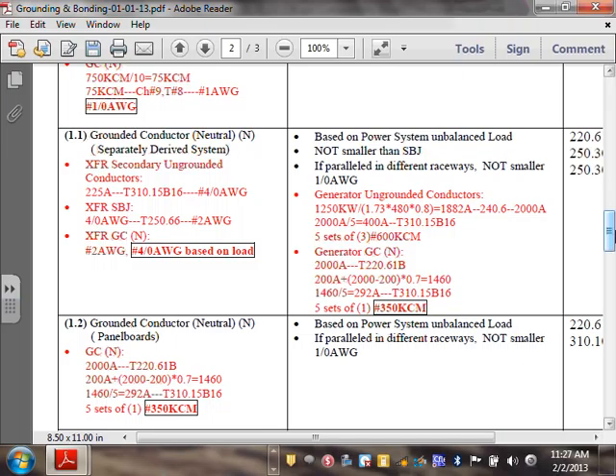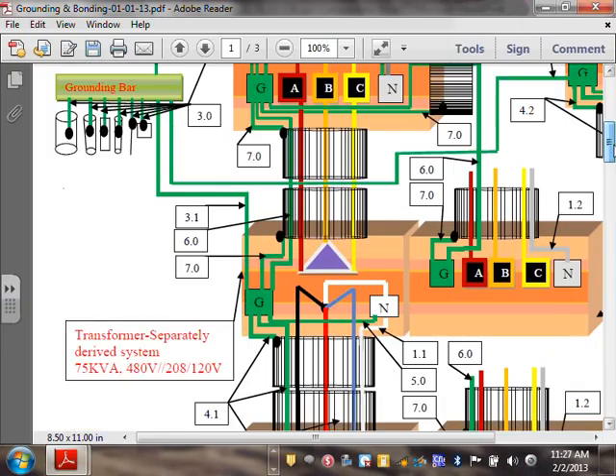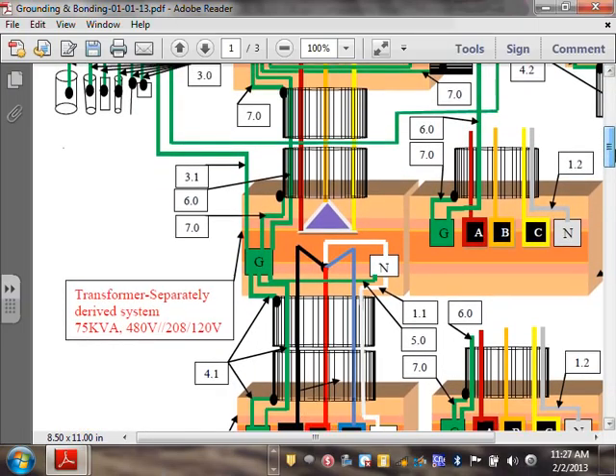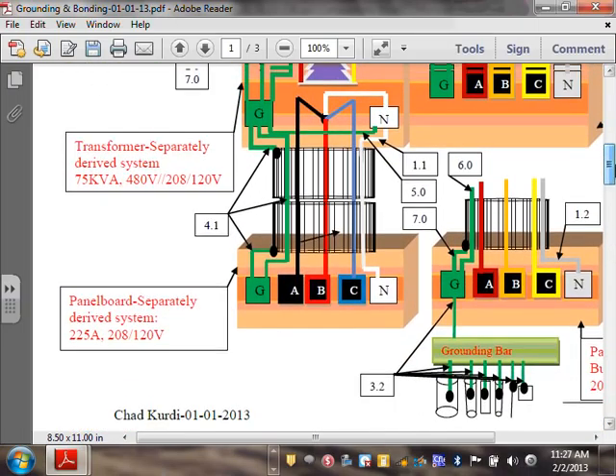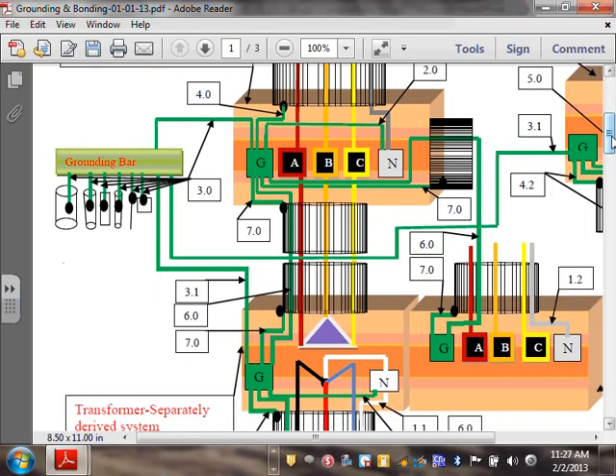Do you guys pull full neutral with these 225 amp? Full neutral, because of harmonics and because of a bunch of other things. Okay, but we talked about the minimum. So let's look at the transformer, guys, and then we'll get into the primary of the transformer. So we got these, we got the neutral.